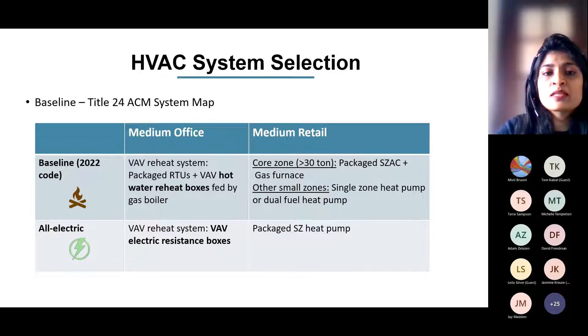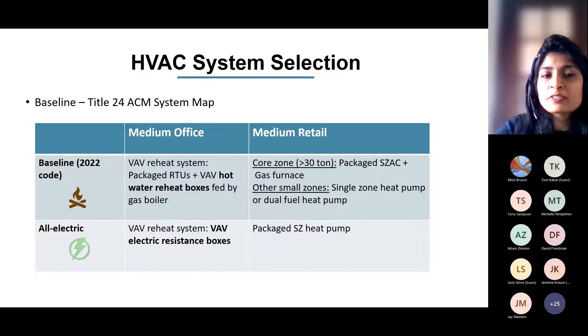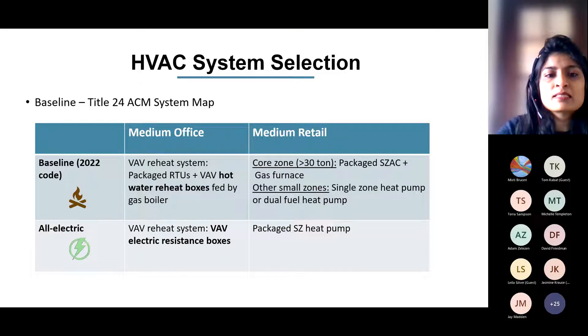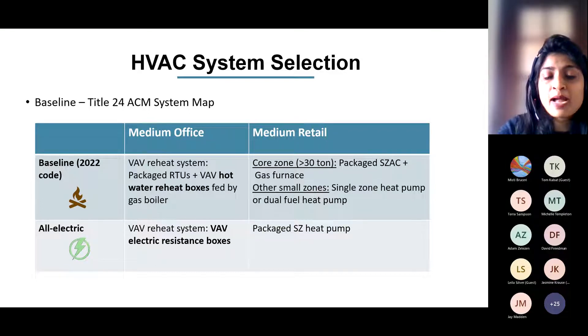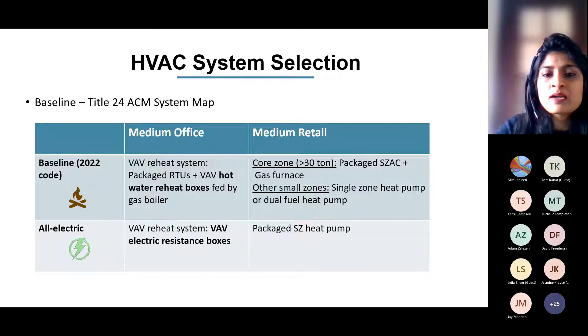For medium retail, there have been some updates in the 2022 code where systems with certain capacity are already required to be heat pump. Most small zones already have single-zone heat pump in the baseline, whereas the core zone, with capacity between 30 to 40 tons, is assumed to have a packaged single-zone AC unit plus gas furnace. Climate zones 1 and 16 require dual-fuel heat pump for certain capacity. The all-electric scenario uses single-zone heat pump for all zones.